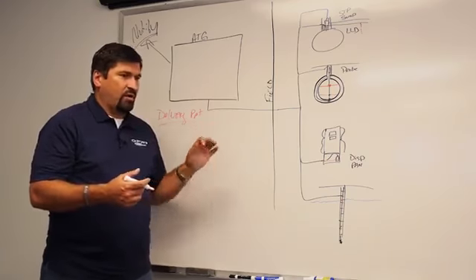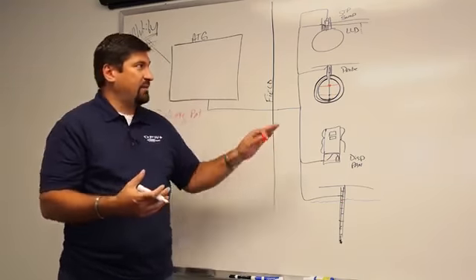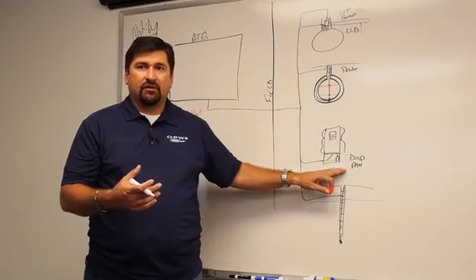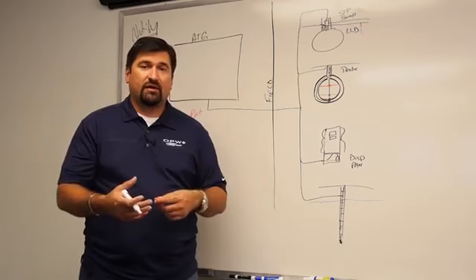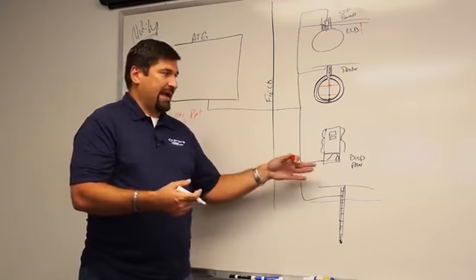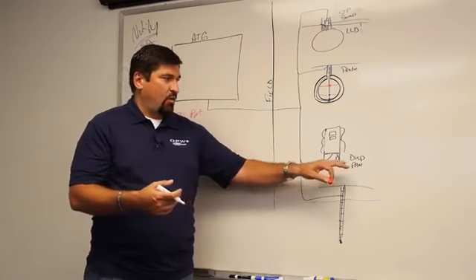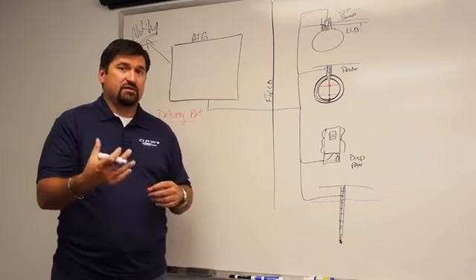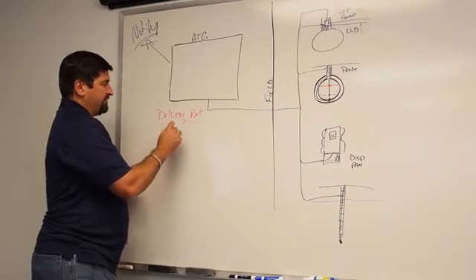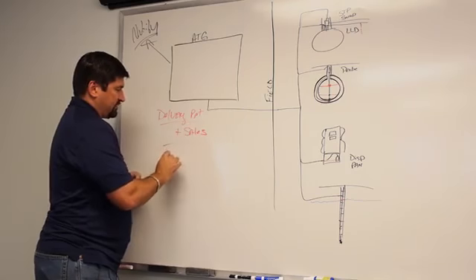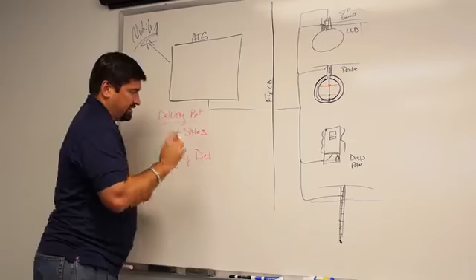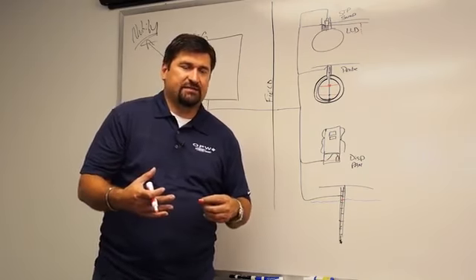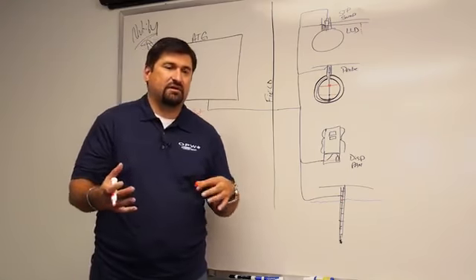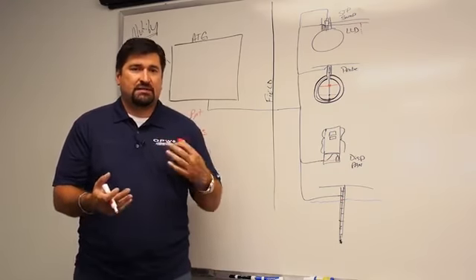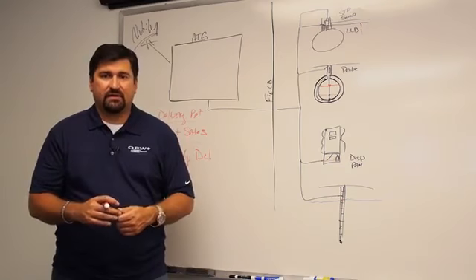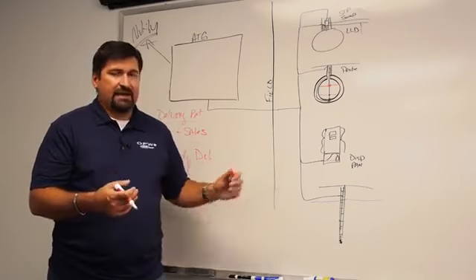Now, this delivery report is going to be inaccurate, because people will be dispensing during a delivery. Any product that is dispensed during a delivery will not be captured. The only way to capture that is by doing what we call reconciliation, where you're tying the actual sales of the dispensers into the gauge, so that your delivery report plus the dispensed product equals an adjusted delivery. That's mainly what people are using the ATG for today: monitoring their deliveries to make sure they're reconciling, tapping into the sales, monitoring what was being delivered into the tank physically, bringing the two together, and creating a reconciliation.